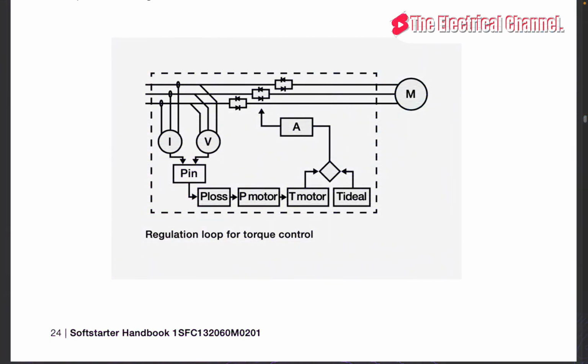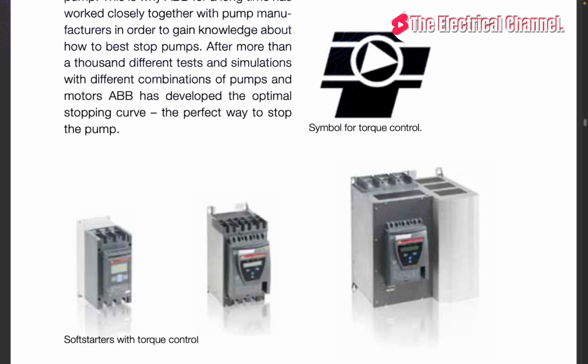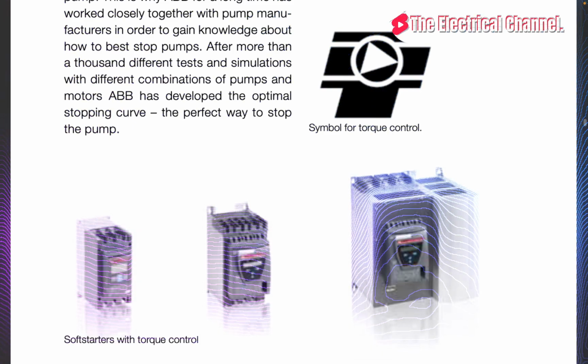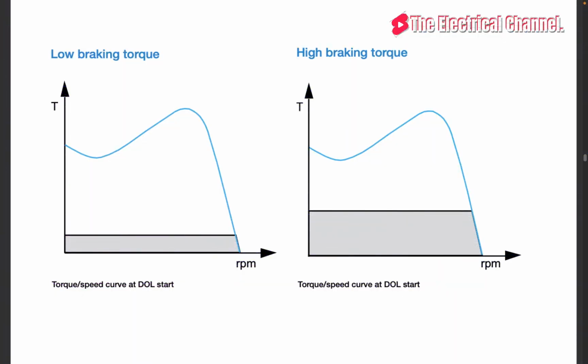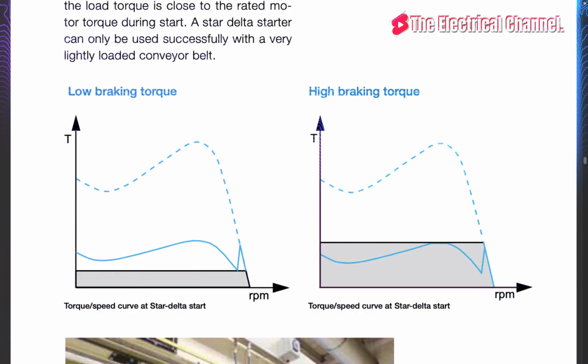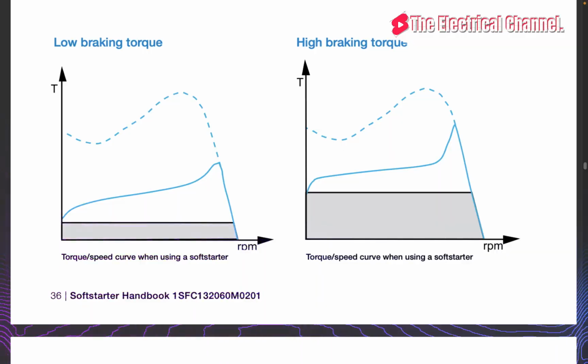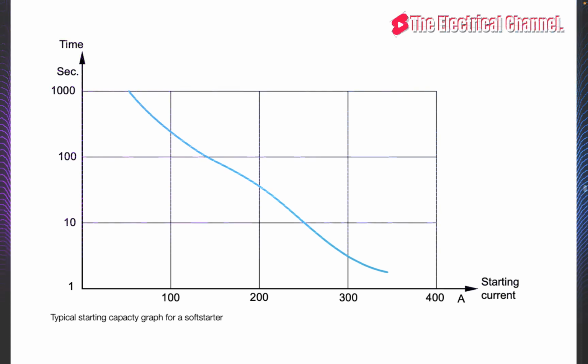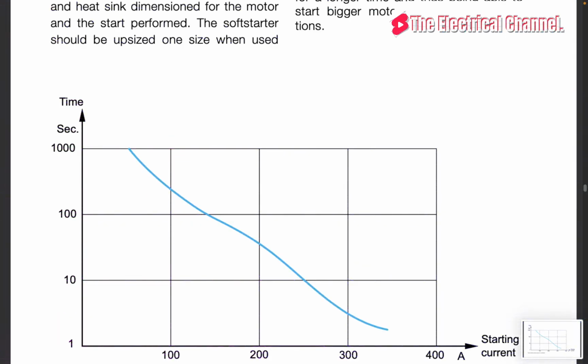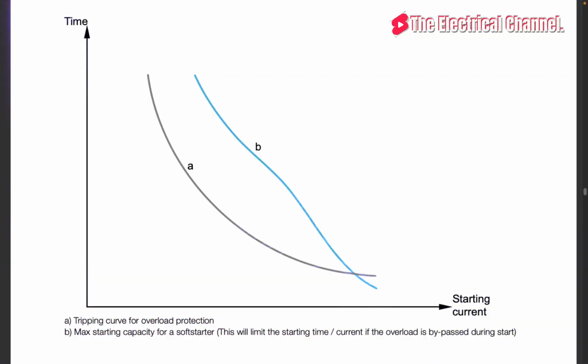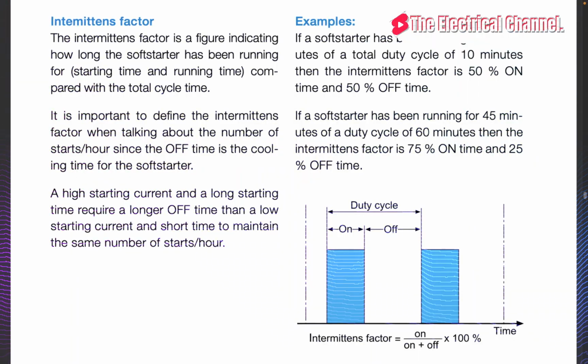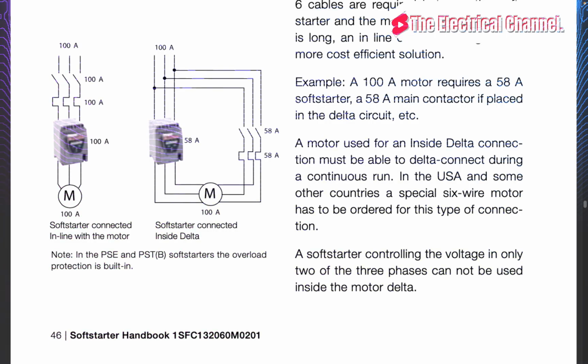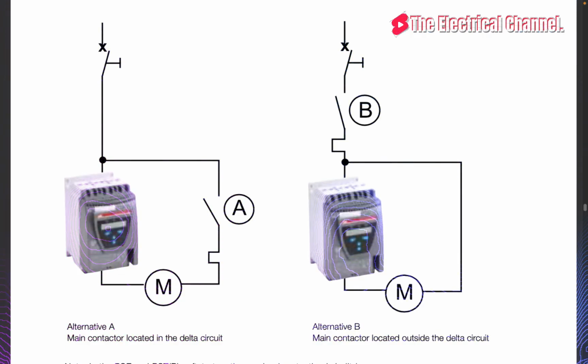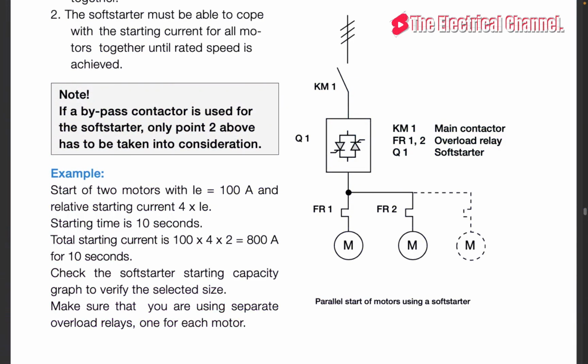Slightly unbalanced currents during start. When using a three-phase control softstarter, the starting current will be balanced between the three phases. When using a two-phase control softstarter, however, the current will be higher in the phase that is not controlled and lower in the other two phases. This has the effect that the maximum current in one phase is higher with a two-phase control softstarter compared with a three-phase control softstarter. This imbalance will only appear during the short time of the start and the stop. During continuous run, the currents will be balanced.